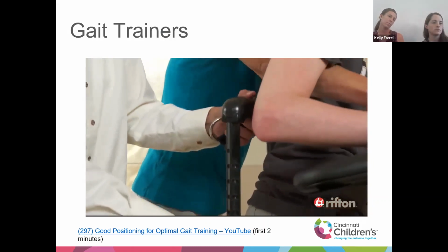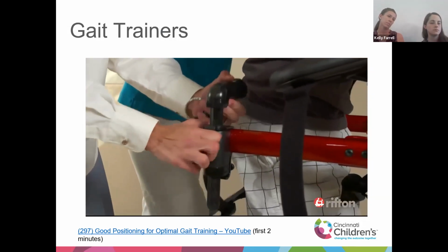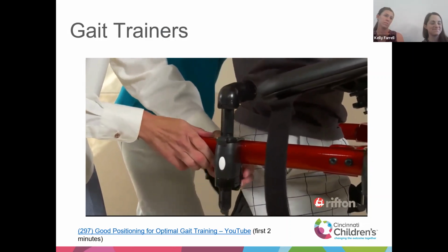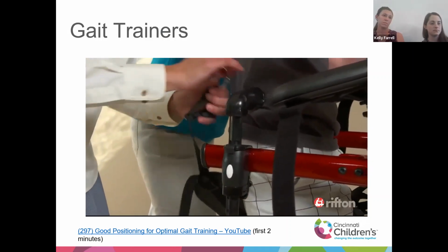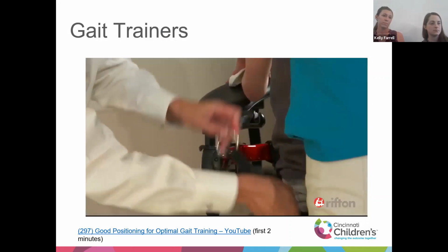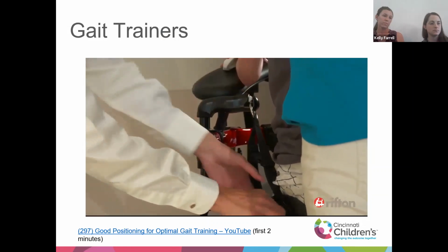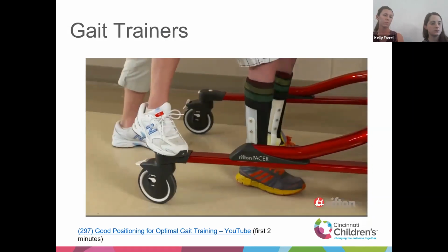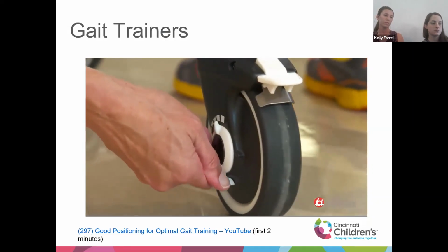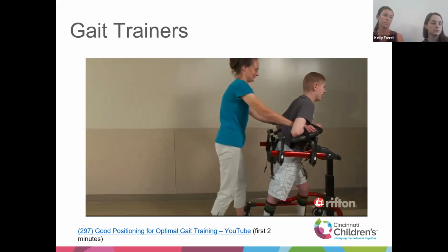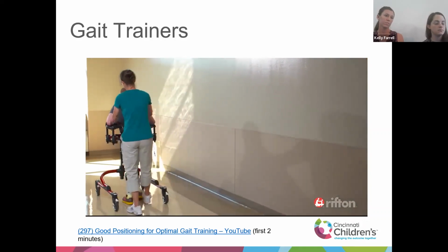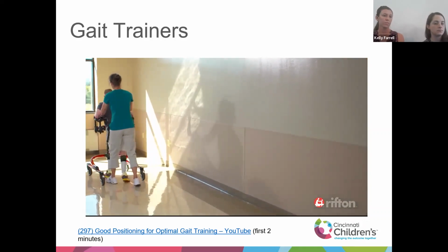For the pelvic support, we moved the clamp of the handhold farther forward. The handhold itself is placed to point inward so the pelvic support straps are closer to Scott's hips. With the straps tightened, the pelvic support will now provide better control. We engaged the swivel lock on the rear casters and set the drag with increased resistance to help Scott gain better control of the frame while walking. With these adjustments, Scott walks in a more upright position and with far better control.